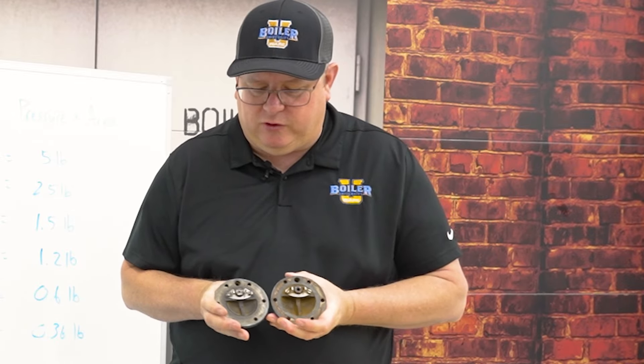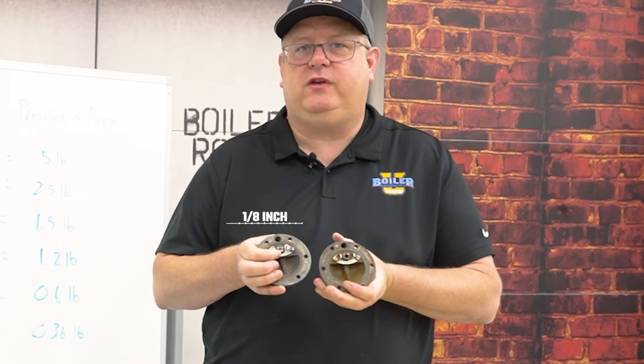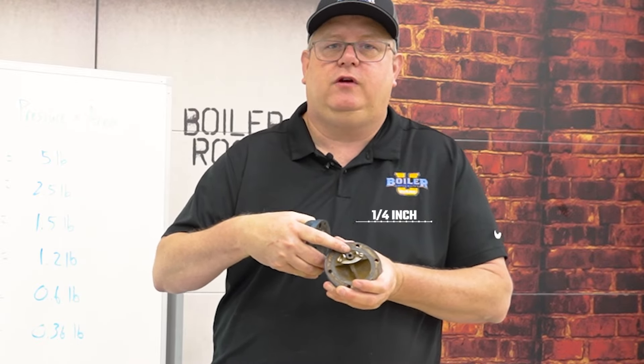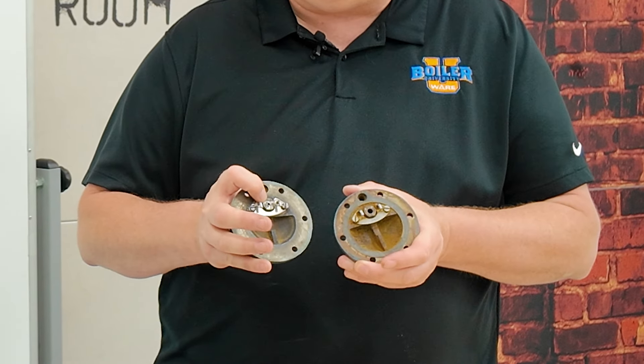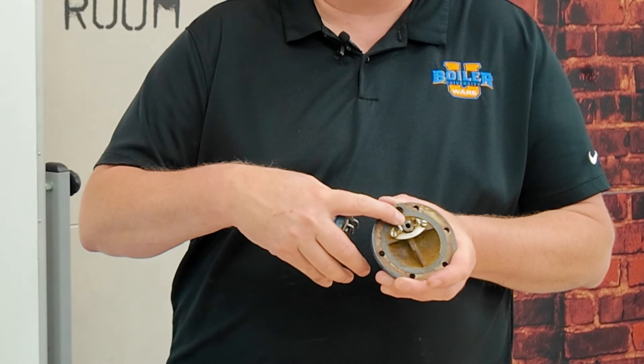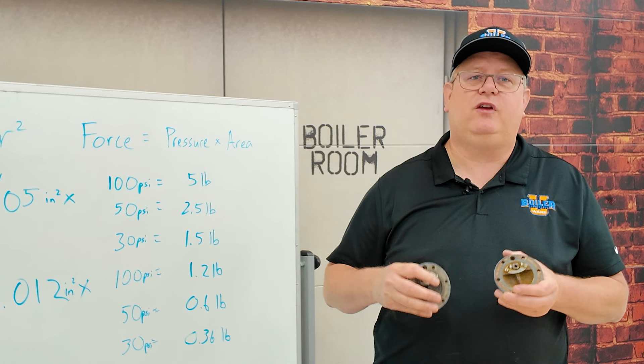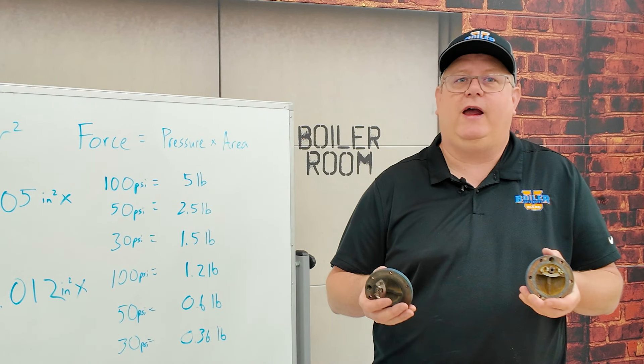If I look at two inverted bucket traps, one has an internal orifice that's an eighth inch, one is a quarter inch. We get more capacity the larger the orifice, but we have to worry about the pressure we're operating at and the force that's applied. Because the larger the seat, the more force — when the trap is closed — holding it shut. And that actually limits the functional range of a trap.